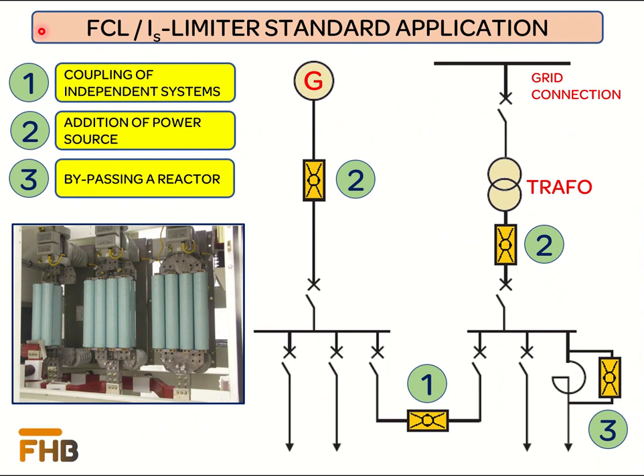In the power network, fault current limiters can be installed in three different configurations. If installed in the bus section, it is mainly used to isolate two sections of the power system for containment of short circuit current within levels agreed with the rated short circuit current of installed equipment like switchgear, current transformers, cables, and so on. It can be installed in series with the power source to restrain generators and transformers from contributing to short circuit current under fault conditions. It can also be installed in parallel with current limiting reactors, with the main purpose of ensuring continuous power supply through the reactor when the limiter is not available after fault clearance and needs replacement of the copper bar and fuse.